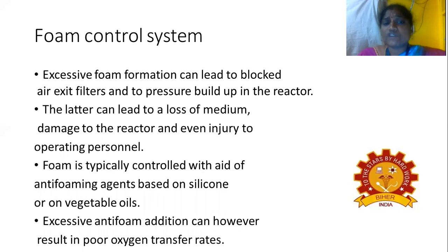Excessive foam formation can lead to blocked air exit filters and to pressure buildup in the reactor. Since the contents inside the reactor are continuously stirred, foam will be formed. This excessive foam formation may lead to some block in the reactor. The latter can lead to a loss of medium, or it may also create damage to the reactor and even injury to the operating personnel.